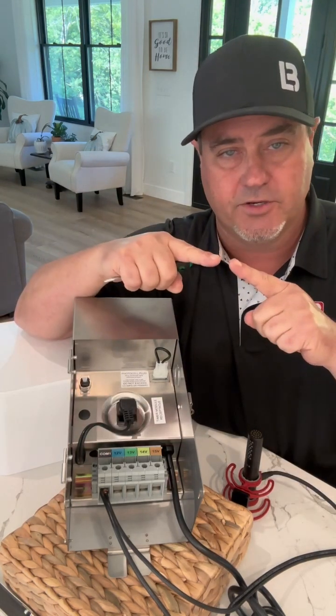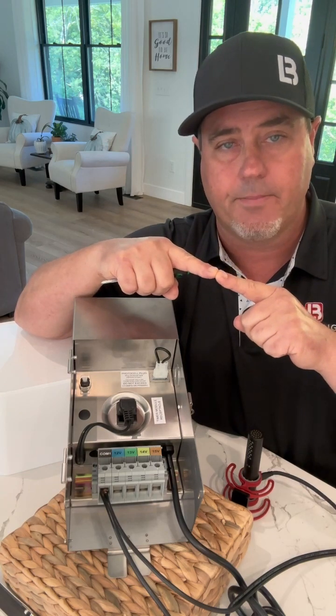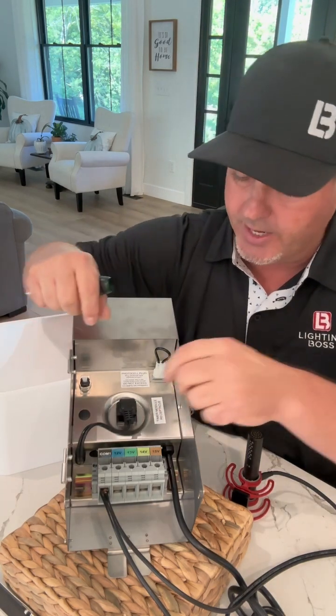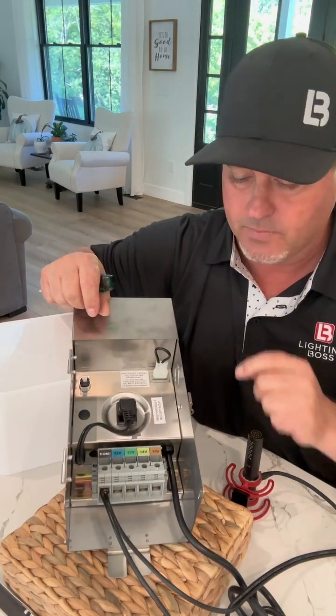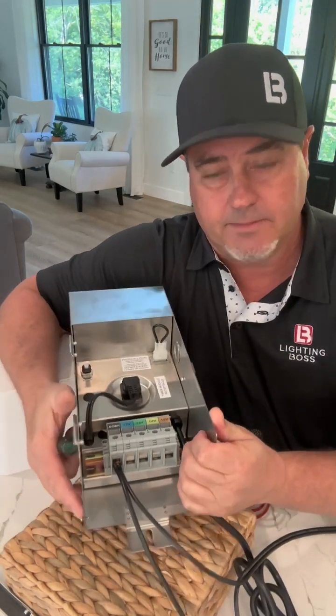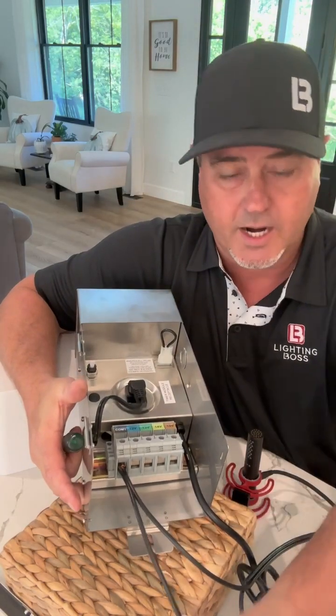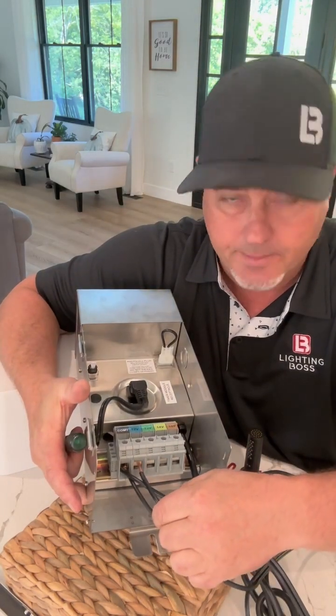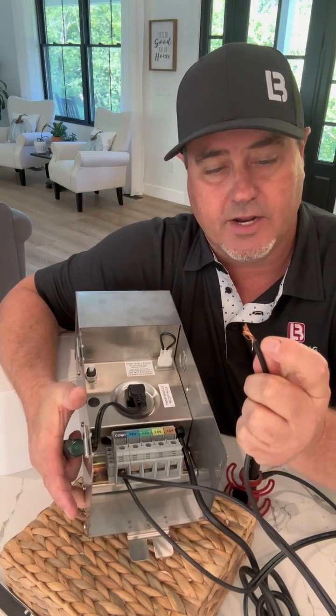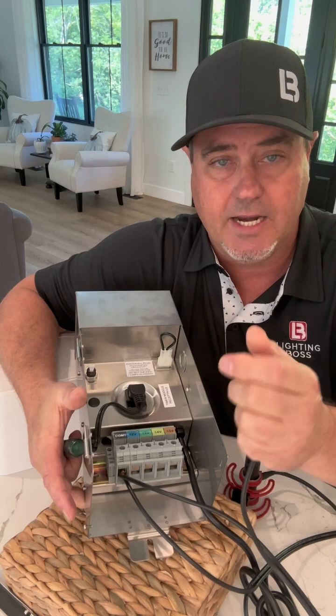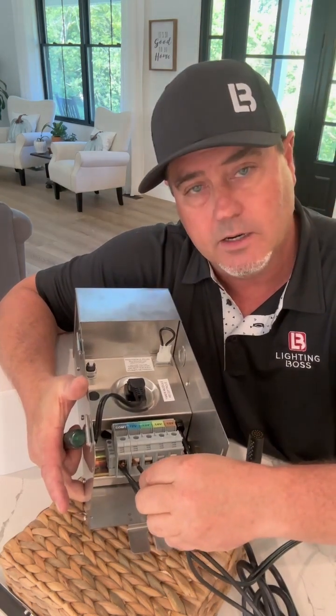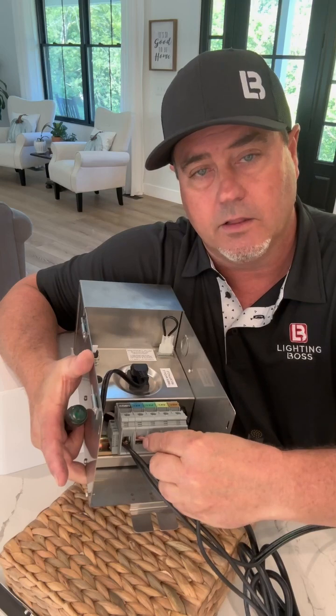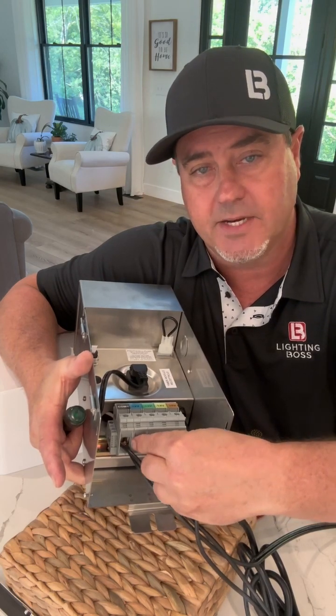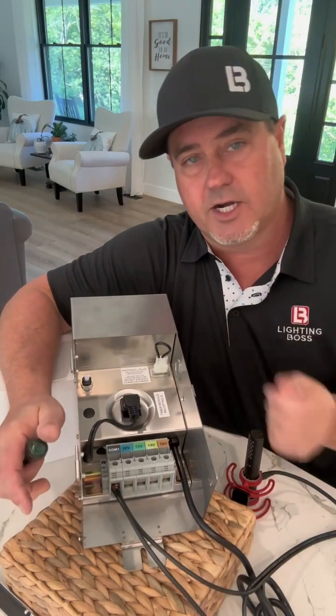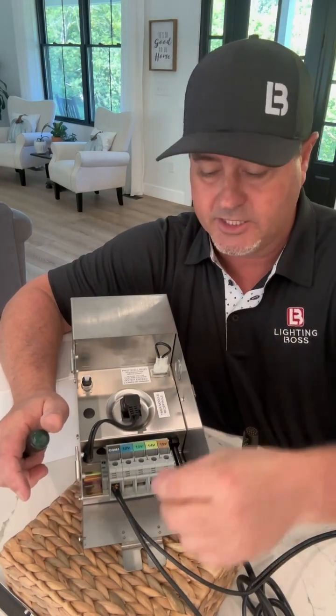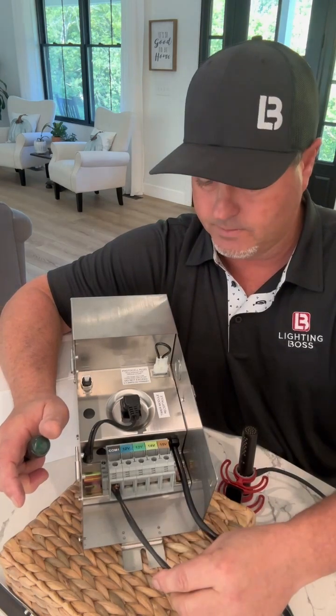Anything where you have the two sides touching, bare copper to bare copper, will create a straight short, just like that. Another place you can sometimes see a short is when you're taking these wires and putting them into this cabinet. This is stranded wire, and you can see it can fray out. So if they're not wound tight and neatly placed in here, sometimes a little bitty fray of just one copper strand might touch the other side, and that can cause a direct short right away. In a worse scenario, it can even burn your wires inside your transformer.